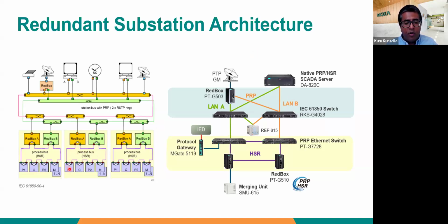In this example, if you look at the bottom, there are multiple IEDs sending signals. Rather than sending a signal only on one side of the ring, you send that same signal both ways. As the intended recipient sees the first signal, there is no need to wait for the second redundant signal.